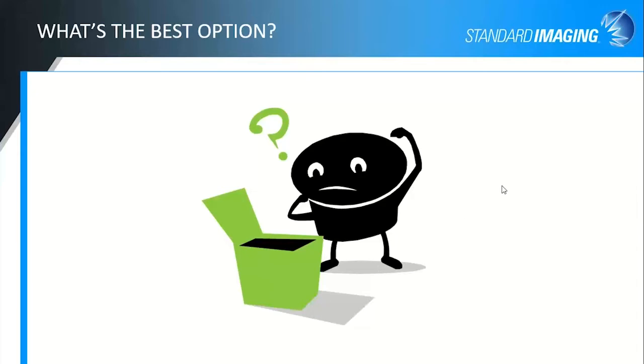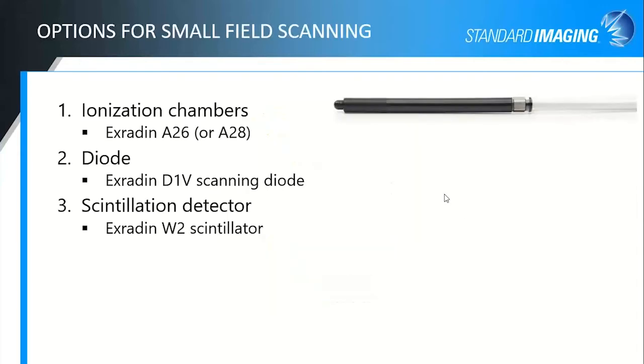So what's the best option for us? We've got three main ones, right? They're ionization chambers, and I'm listing the A26 here, which is our micro-ionization chamber. The A28 is our standard scanning chamber. There are diodes, like the Exradin D1V scanning diode, and then a water equivalent detector, the Exradin W2 Scintillator.